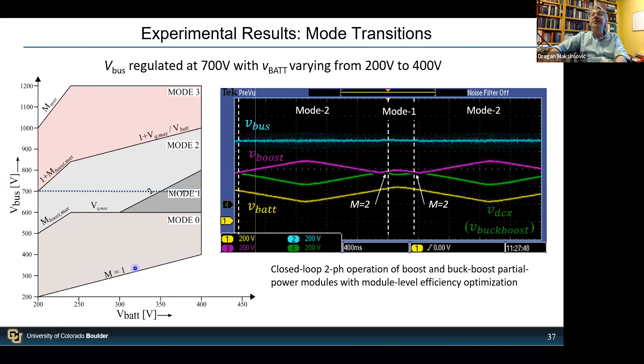This illustrates how the system switches smoothly between modes as the battery voltage varies, while keeping the output voltage constant at 700 volts. We've tested this system moving in all directions, with the voltage up and down for a given battery voltage, or various combinations of battery and bus voltages, all handled by the system controller.